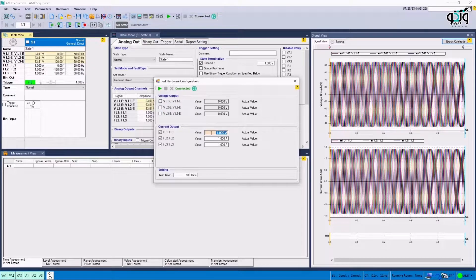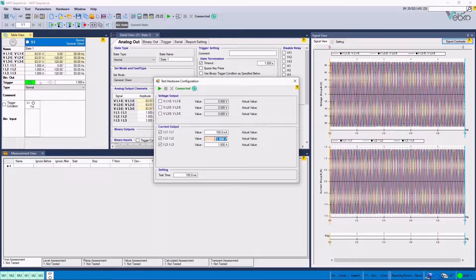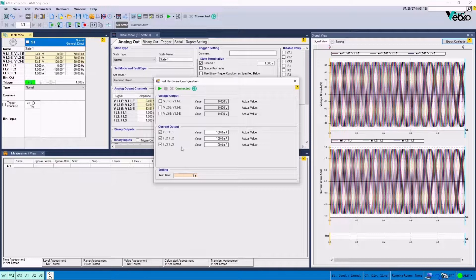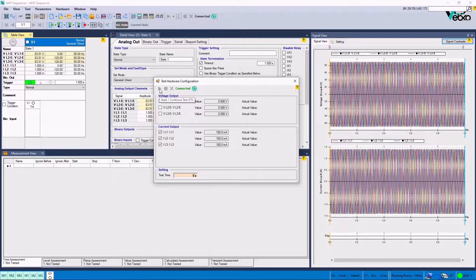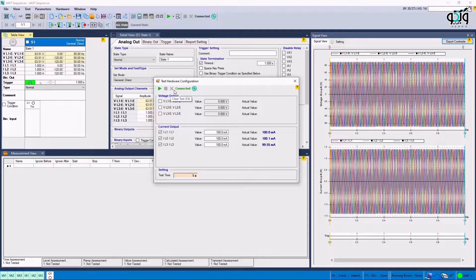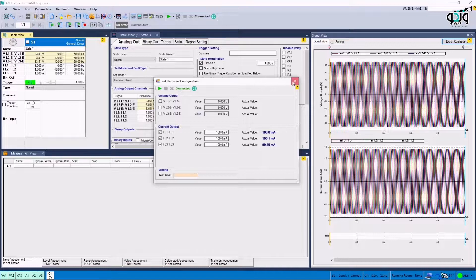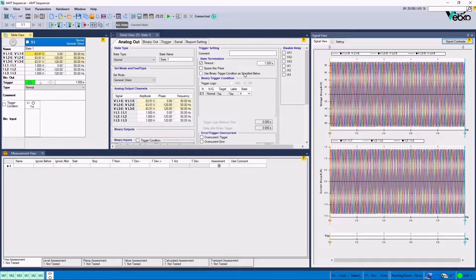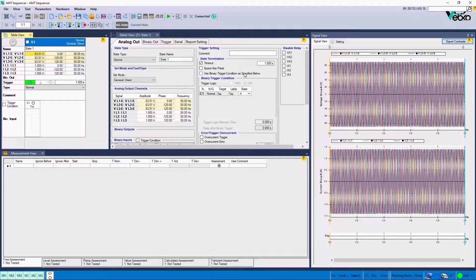Then, the intended current must be specified in Current Output section. Current Injection channels are specified and the injection duration is selected. By clicking on the triangle at the top of the screen, the injection will keep going as long as the specified duration. The first part of the end-to-end test is related to ensuring stability or in other words, that if equal currents are injected from the two sides or an external fault state, a trip is not issued. To test this state, Sequencer Room is opened.